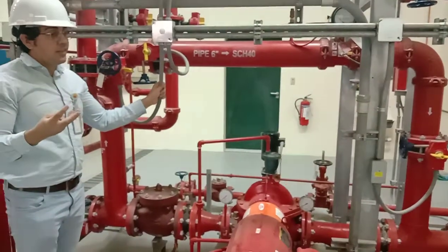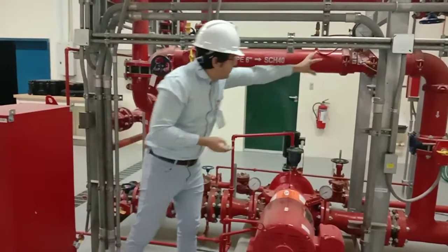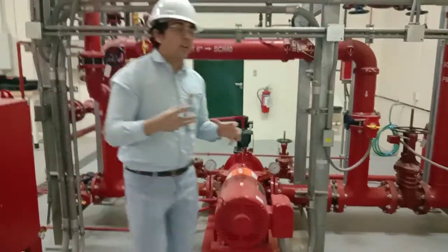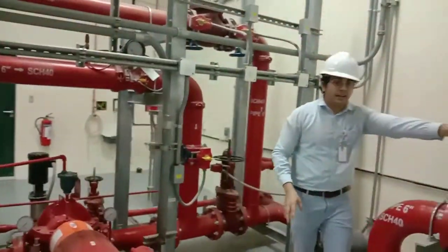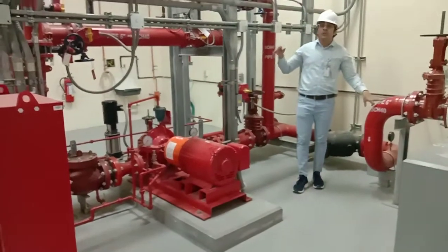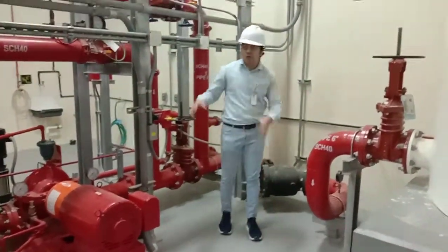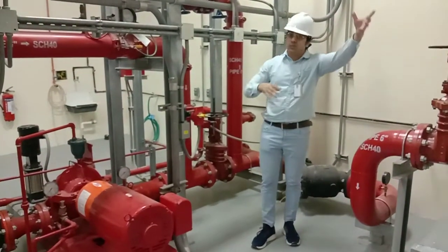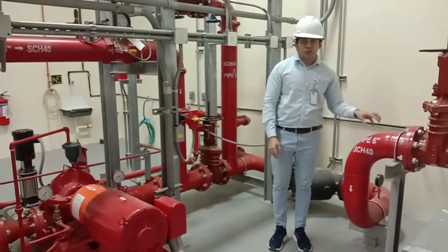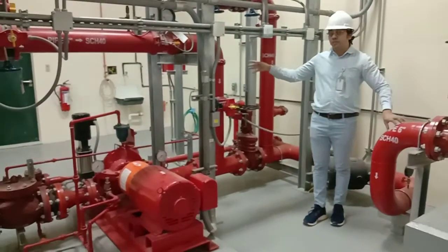So 3 things to discuss: the test header, the flow meters, and the closed loop metering device. Now there is a problem with the closed loop metering device. NFPA 20 says that within 3 years, we need to check the condition of the water supply from the tank, right, through the piping all the way to the suction piping, coming at 150% of the flow at pressure more than 0 psi, right? This is one of the requirements, and we want to check that the suction line is supplying our water at exact condition. So at that moment we need to discharge the water, and check the quality of the water, the capacity of the suction line, and whether after 3 years from the beginning performance test, our suction line is giving the pump supply at 150% of rated capacity.